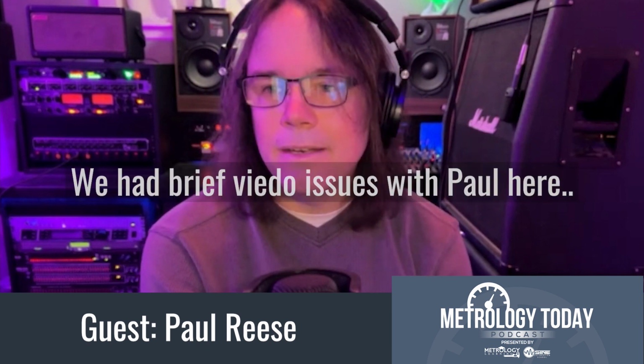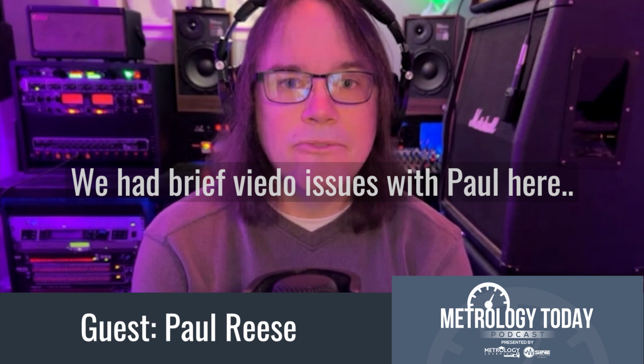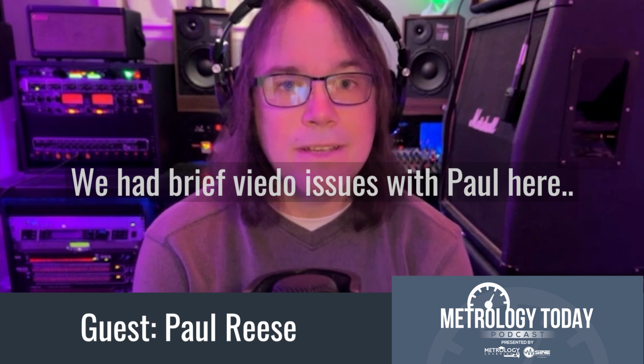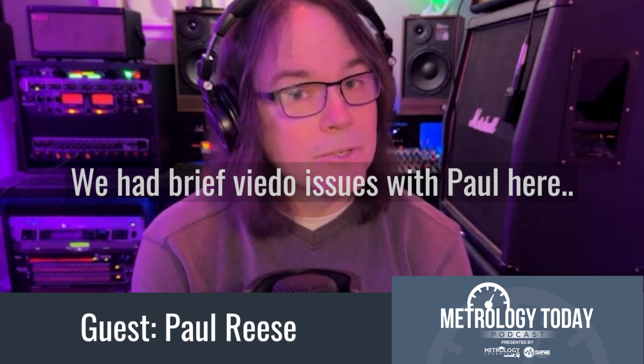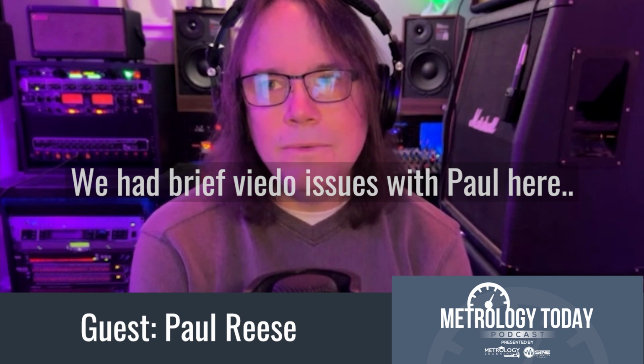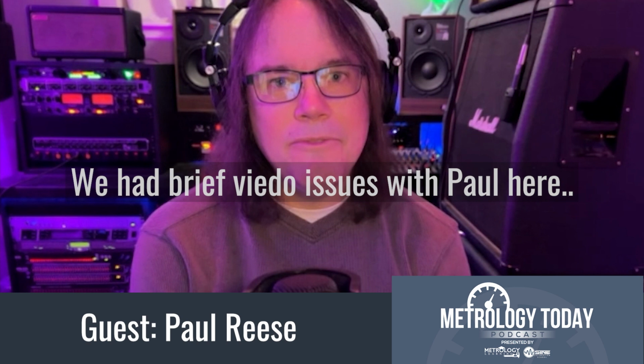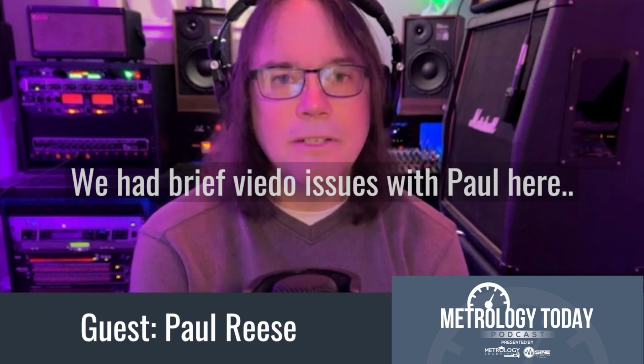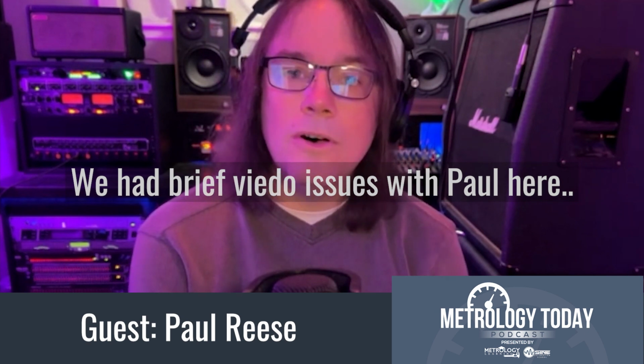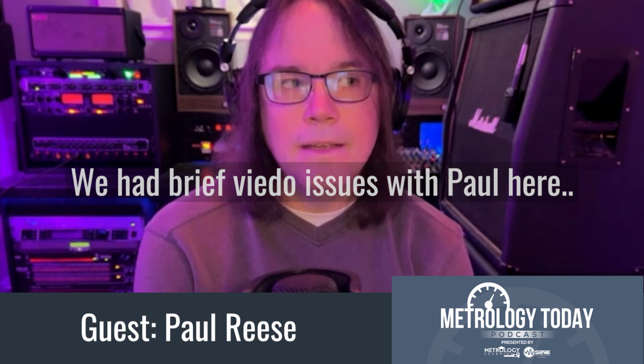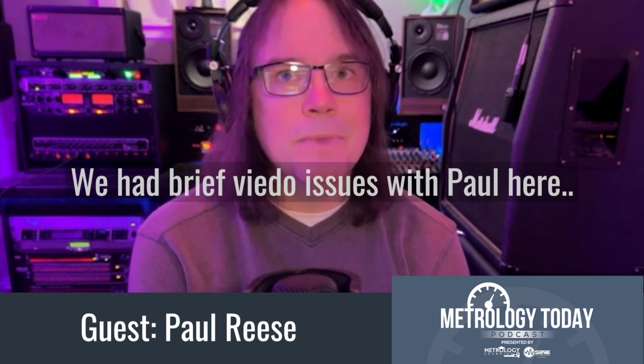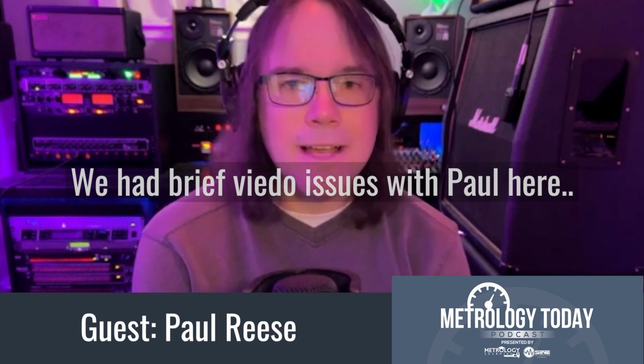So if you look at your reliability history, maybe you calibrate something once per year, and over the last 5 years you might have 5 calibrations of it. You can still do a control chart that way. But if you had the advantage of a long history and a control chart of your end of period reliability, how often is it found in tolerance? And that's over a long enough period that many different technicians have calibrated it, they've used different standards, your own standards have been recalibrated by NIST or whoever it is, and, as Ryan mentioned in the last section, maybe you've used different calibration providers sometimes.